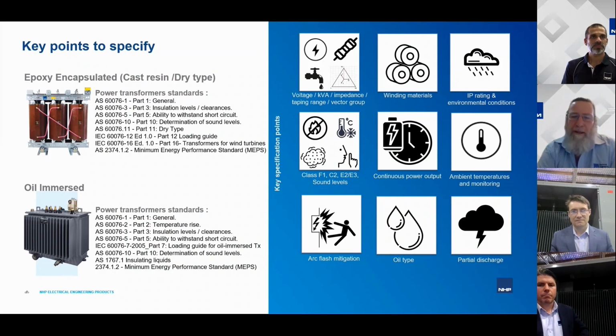Having said that, especially when we come to the cast resin transformers, a lot of the manufacturers have a real preference for using aluminium conductor. And the simple reason for this is that the coefficient of expansion of aluminium compared to the cast resin materials that are used are very, very similar. And so therefore the thermal stresses within the winding as the transformer cycles through different loads and heats and contracts means that the thermal stresses are very, very even with the conductor versus the insulation material. Just something to bear in mind. You can have a good and a bad transformer in either material.